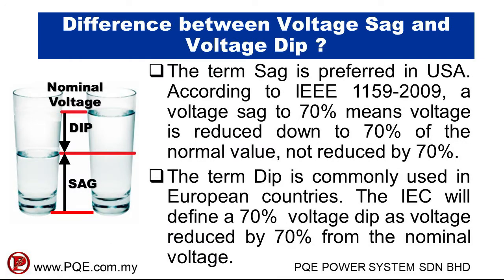The difference between voltage sag and voltage dip: the term 'sag' is preferred in the USA. According to IEEE 1159-2009, a voltage sag to 70% means voltage is reduced down to 70% of the nominal value, not reduced by 70%. The term 'voltage dip' is used in European countries, where IEC defines a 70% voltage dip as voltage reduced by 70% from the nominal voltage.